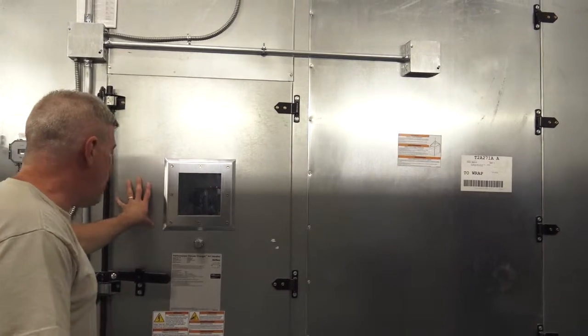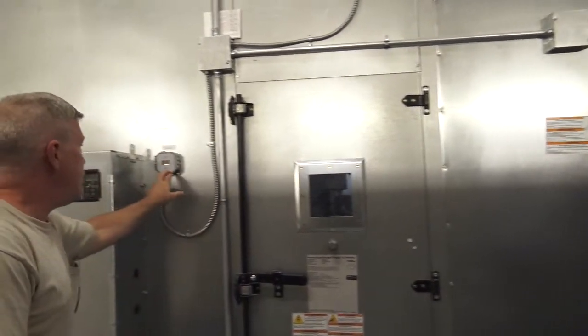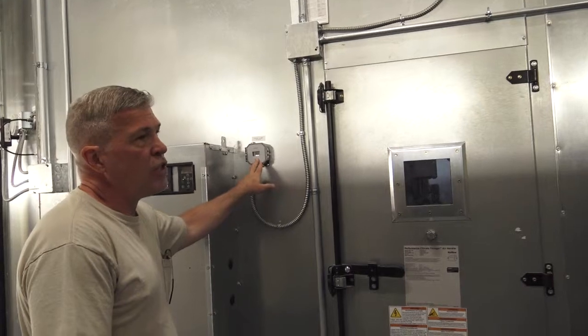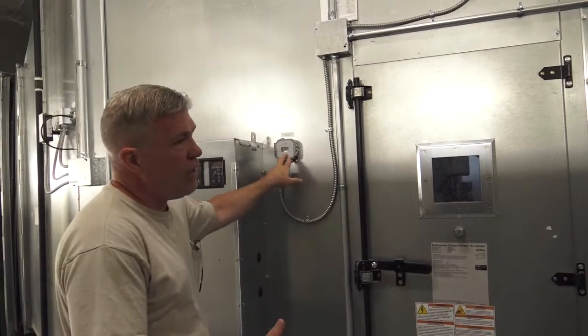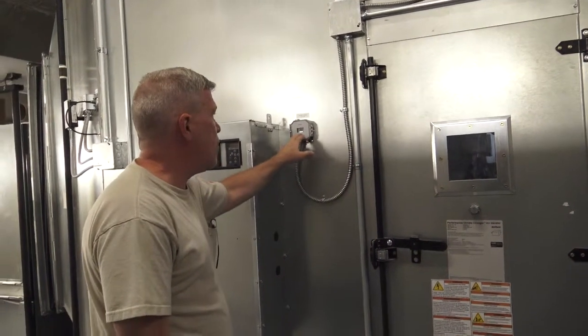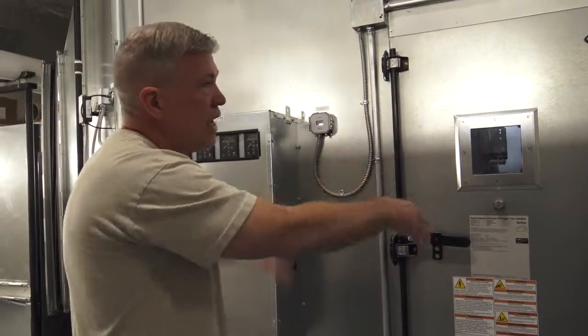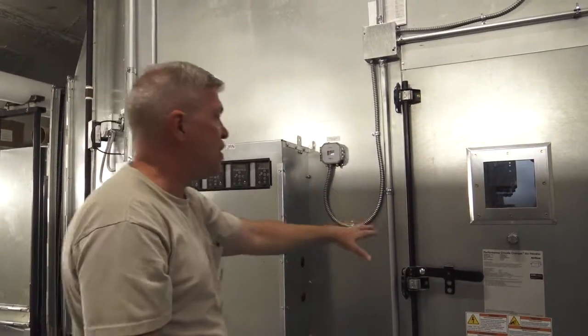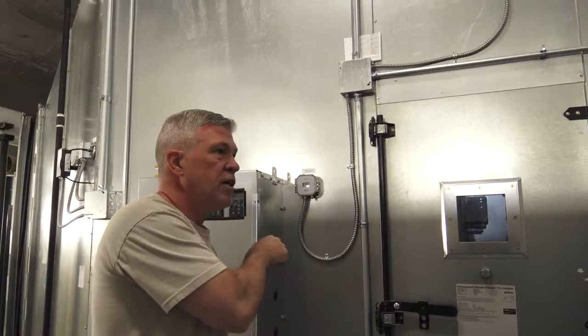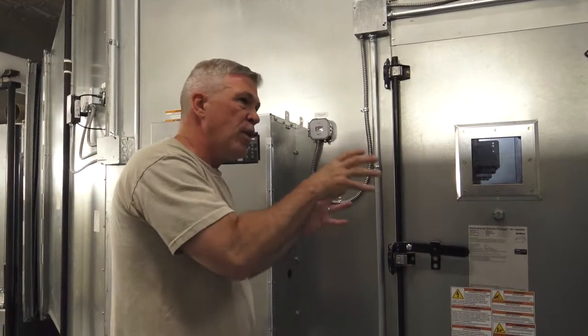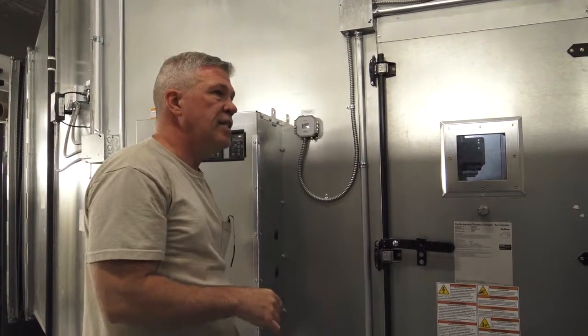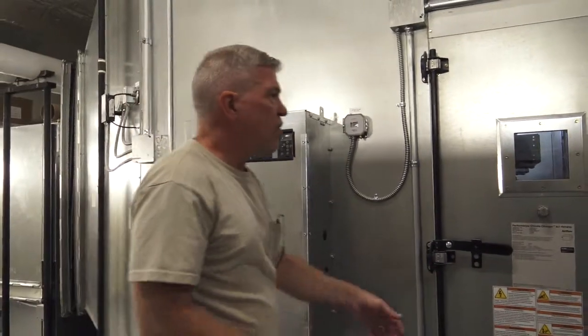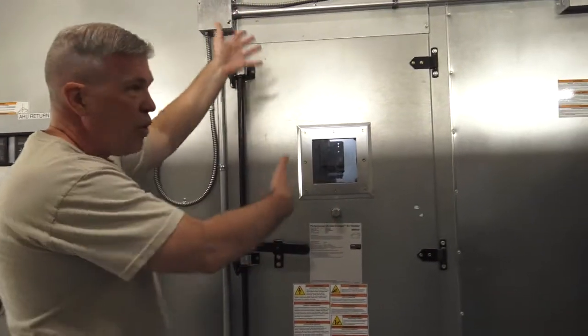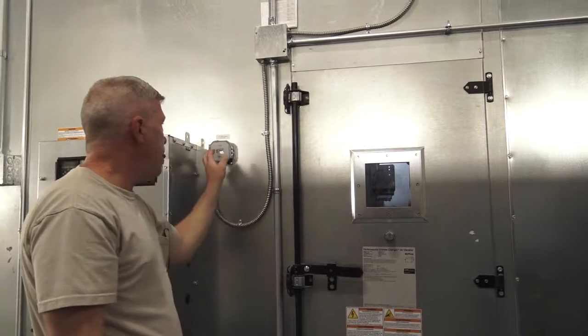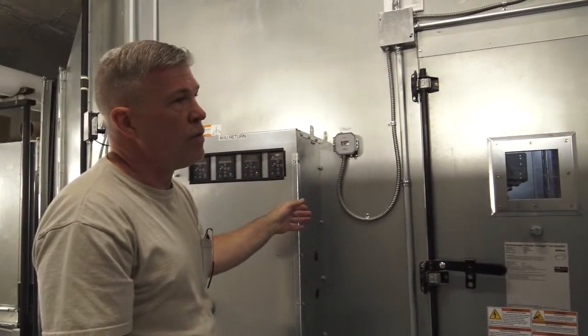But also your return fans, your return plenum differential. Again, primarily there for monitoring, but if for some reason, say these dampers are both closed at the same time and this differential shoots up, it will shut the return fan down. From the graphic, there's a point you can reset that to get this all back running again. So if your actuators fail and these are both sitting closed, this will shut this section down.